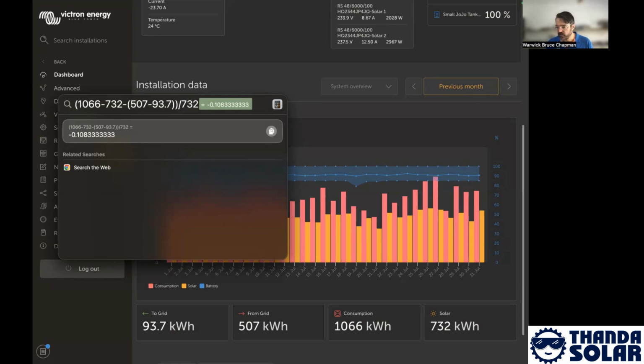But as I mentioned, there are other factors in play. The multi-RS site by definition has the PV wired internally, so it isn't going to a separate MPPT down to a bus bar. So there's potential for wiring losses in the Quattro-based system, whereas this one has less potential for that. The one might be operating in a warmer room than the other one. A cooler inverter is definitely a more efficient inverter. So it's an indicative example for you, just so that we can help understand these concepts. But if we did a broader survey of transformer-based sites versus RS-based sites, I think we would find a very clear trend.